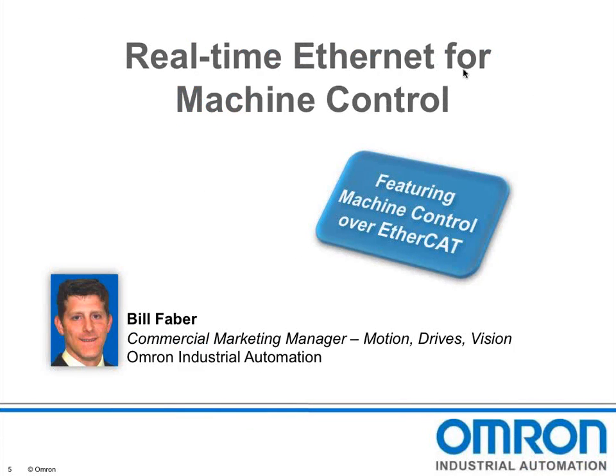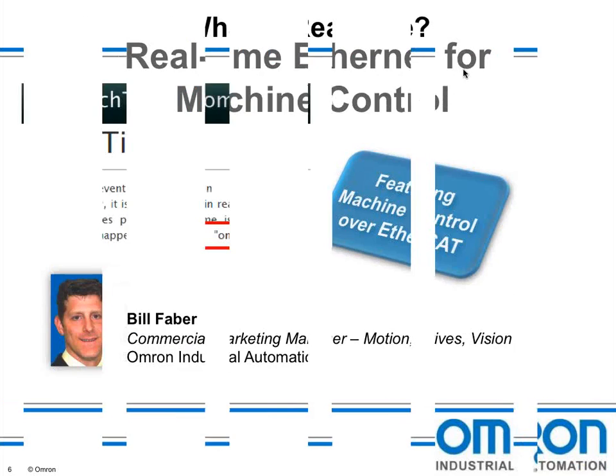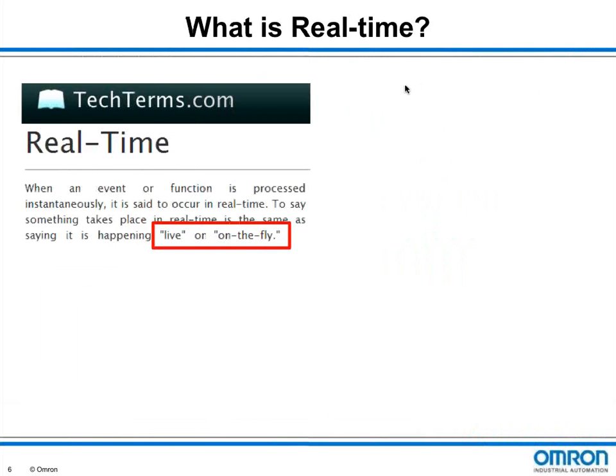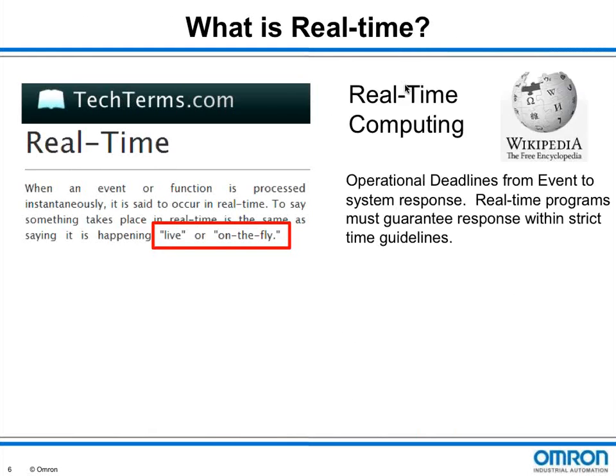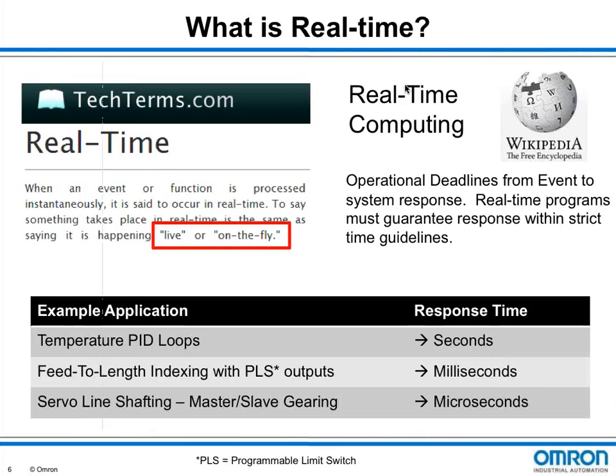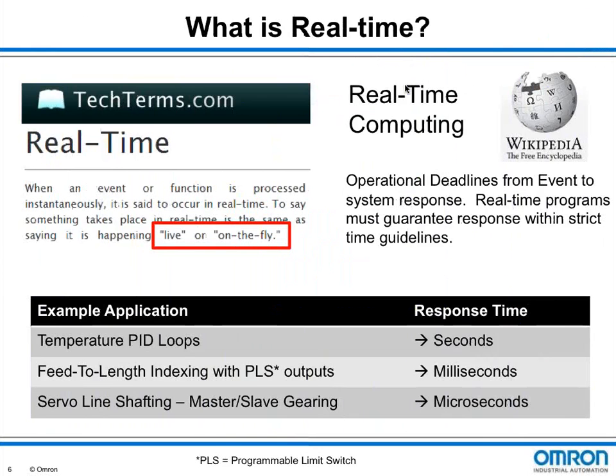Thanks, Dave. Real-time Ethernet for machine control — so what is real-time? According to tech terms, it's live or on the fly. According to Wikipedia, it has to do with operational deadlines or guaranteeing response within specific time guidelines. It's really a relative term unless put into context. In machine control, real-time could mean seconds for PID loops like controlling oven temperature, milliseconds for I/O coordination with simple indexing, or microseconds for tight coordination of several axes on a master-slave line shaft application.